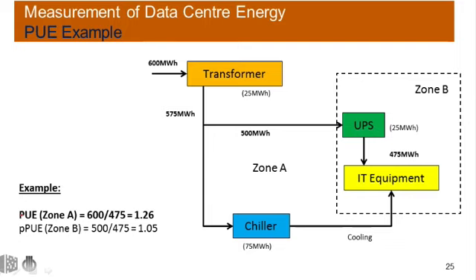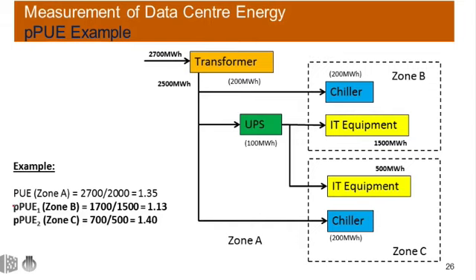The PUE considers Zone A, everything that you can see on that graphic. So, for example, going into the transformer, you can see we have 600 megawatt hours, and if you look at the example calculation, the first figure is 600. Then going down to the IT equipment level, we have 475 megawatt hours. So it's fairly straightforward to see that PUE for this facility would be 1.26.